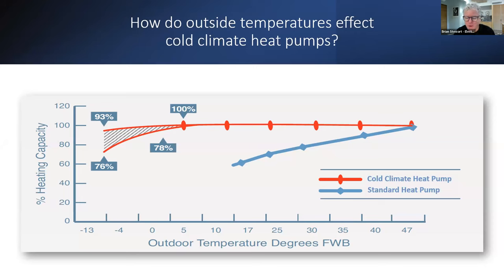Because that's an essential part of this whole load calculation thing that a good HVAC installer is going to be doing, right? Yeah. So as the temperature drops, the heat demand goes higher, but with a standard heat pump, it's an inverse relationship. As the temperature drops, it's less capable of delivering heat into the house. And so that can be great down to that 40 degrees, 30 degrees, 20 degrees type of range. That could be a decent matchup with a dual fuel system consideration. And that's probably where we're going to see a lot of expansion in the heat pump market, is that dual fuel application. So another heating system, whether it be a natural gas furnace or other, that is tied into the control system, can take over and start to heat that house as the temperature drops. That is a viable pathway that we as an industry see significant growth in.